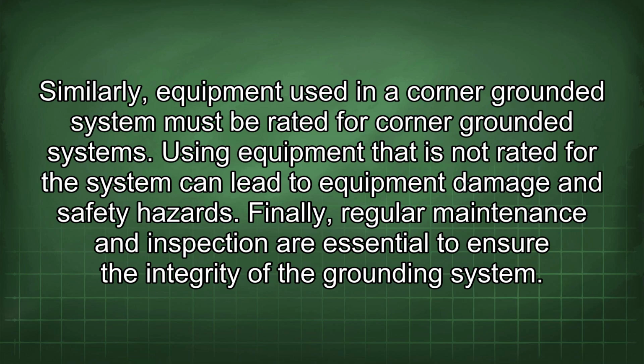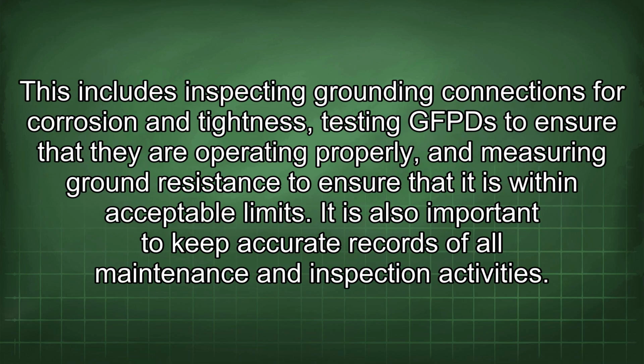Finally, regular maintenance and inspection are essential to ensure the integrity of the grounding system. This includes inspecting grounding connections for corrosion and tightness, testing GFPDs to ensure that they are operating properly, and measuring ground resistance to ensure that it is within acceptable limits. It is also important to keep accurate records of all maintenance and inspection activities.